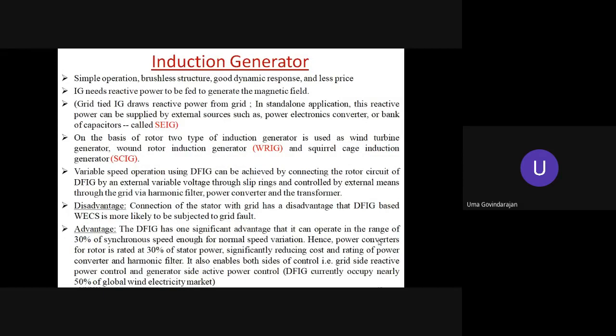The next one is the induction generator. Simple operation, brushless structure, good dynamic response, and less price. The IG needs reactive power to be fed to generate a magnetic field. Okay, that's what I told earlier. A grid-tied induction generator draws reactive power from the grid. In standalone operation, which is not a grid-tied operation, this reactive power can be supplied by external sources such as a power electronic converter or a capacitor bank.